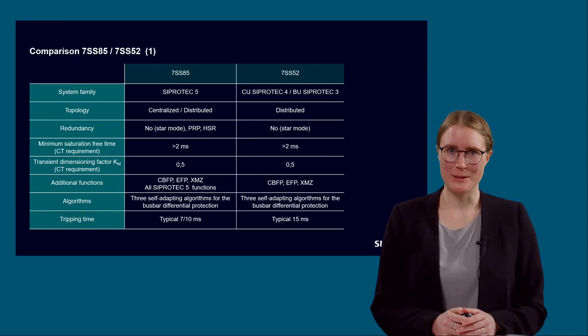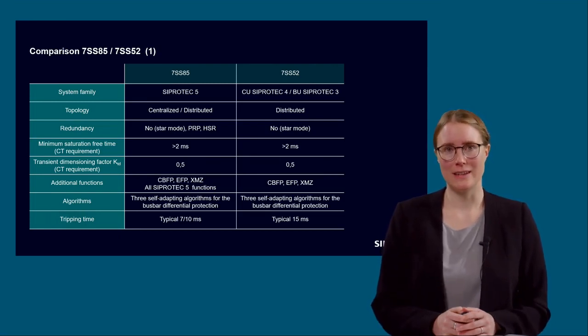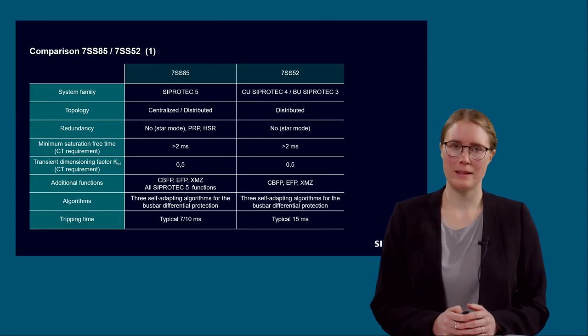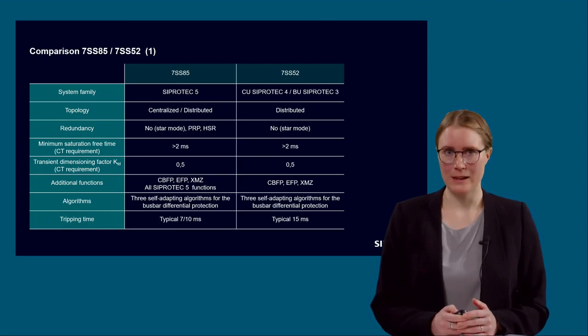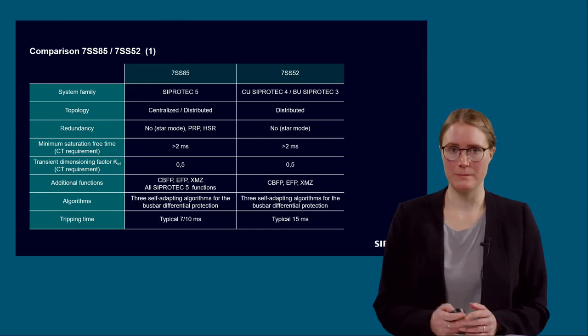The tripping times of SIPROTEC 5 are a little bit lower than with SIPROTEC 4. In the 7SS52, the minimum tripping time for high current internal faults is 15 milliseconds. For lower currents with DC offset, higher tripping times are possible. With the 7SS85, tripping times of 7 milliseconds with the centralized system and 10 milliseconds for the distributed systems are possible.